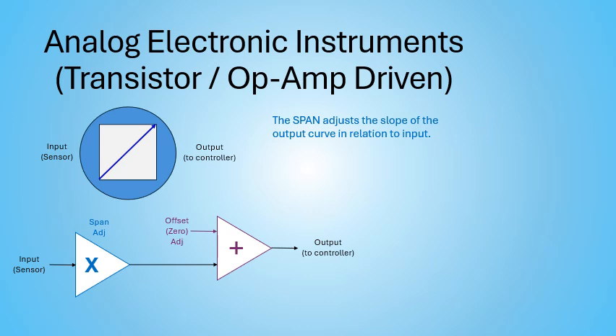Okay, so the older analog electronic instruments typically were driven with operational amplifiers, these transistor-based chips, basically, kind of the early days when they were really just starting to get this electronics thing all lined out. And in order to convert the sensor to an output signal that goes to the controller, your 4 to 20 or whatever, it was typically for linear signals. There's a typical setup. You have to multiply it, and then you have an adder that moves it up or down. And with those two, you can get that straight line, that conversion, if you will, or transfer function anywhere you want.